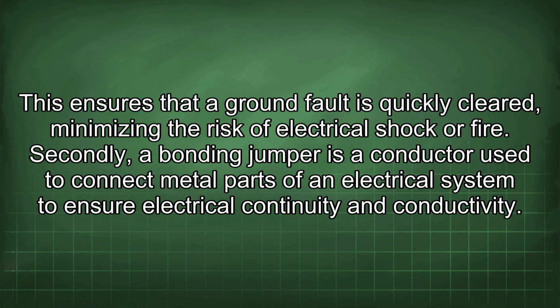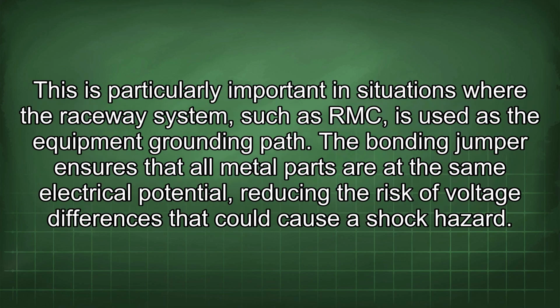Secondly, a bonding jumper is a conductor used to connect metal parts of an electrical system to ensure electrical continuity and conductivity. This is particularly important in situations where the raceway system, such as RMC, is used as the equipment grounding path. The bonding jumper ensures that all metal parts are at the same electrical potential, reducing the risk of voltage differences that could cause a shock hazard.